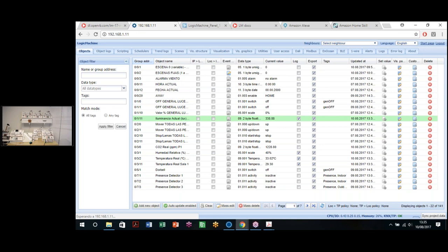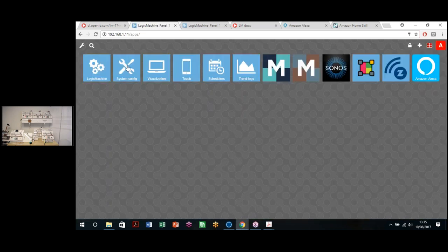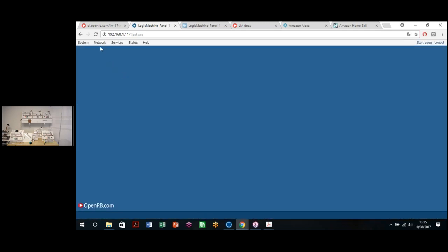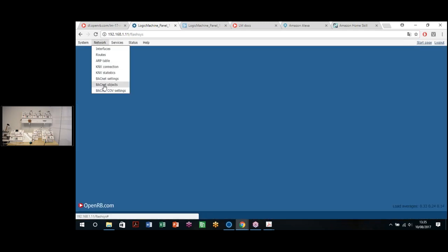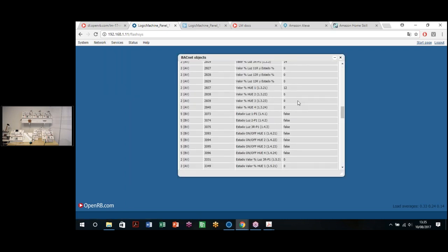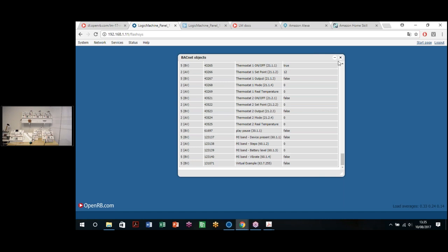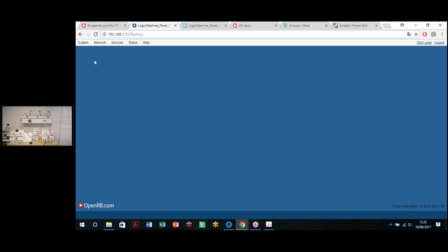So again, we can check here how many data points are exported in BACnet, okay? Let's go again to network, and not in settings but in objects. We can see a list of all the objects that we have in BACnet for this device. We have done exactly the same for the rest of the devices.